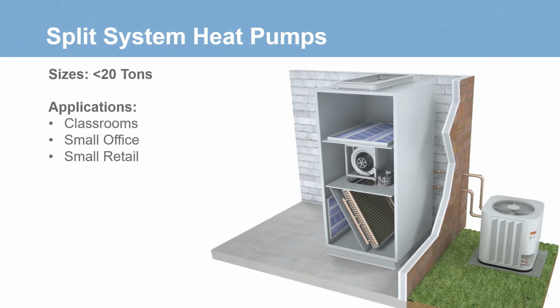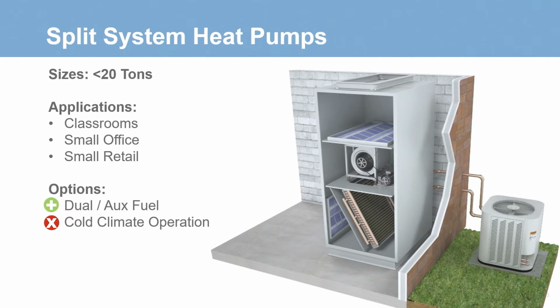When designing with these systems, ambient minimums are a concern. Most split system heat pumps do not have cold climate capability, so the heating capacity will be reduced or even eliminated when ambient temperatures fall below 32 degrees. To help with this situation, dual and auxiliary fuel options are available from most manufacturers.